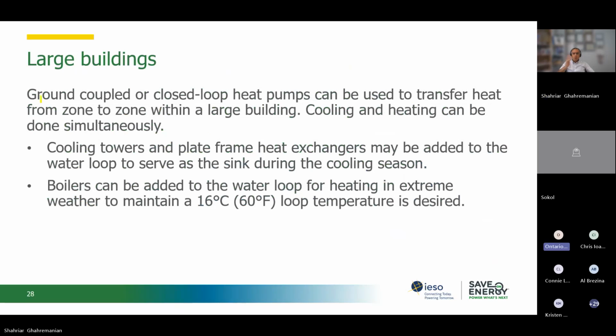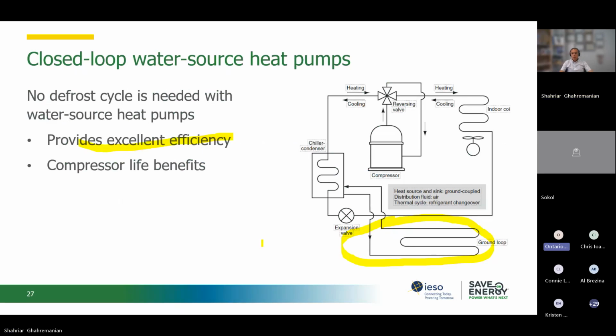Can you explain a little bit what makes a ground source heat pump more efficient than an air source? Yeah, there are two reasons. The first one is that we have high conductivity and high heat capacity, either in the ground or in the water that we use. I have a slide that compares air to water, and in that slide you will see that water has almost 25 times the heat conductivity of air. The same goes for the heat capacity, which is 4 to 1. The heat capacity of water is 4.2, and for air it is almost 1.